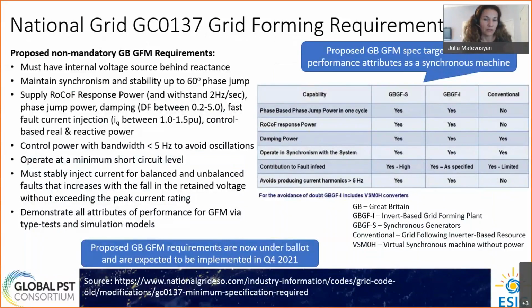These requirements were then converted to a grid code proposal, and these requirements are proposed as non-mandatory requirements. And the idea is that after requirements are approved, in parallel there will be development of a market for system services. Essentially, again, provision of system strength and inertia, and these will be commercial markets that will incentivize these capabilities. So the idea of a grid code requirement is just to say, if you're providing this service, these are capabilities that you need to have.